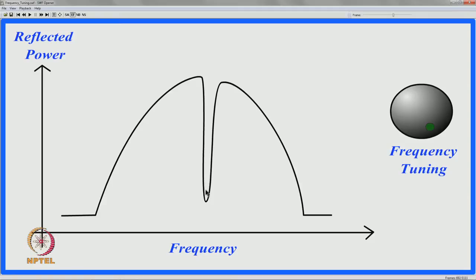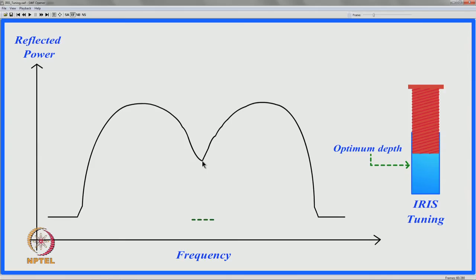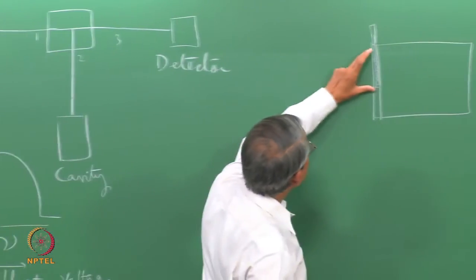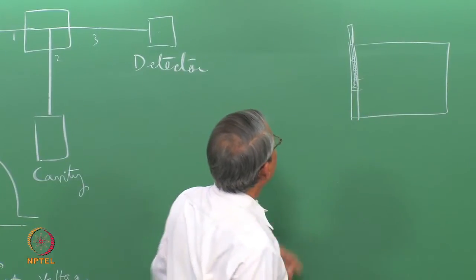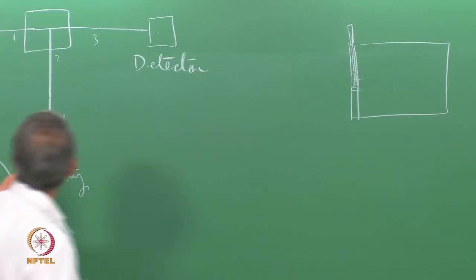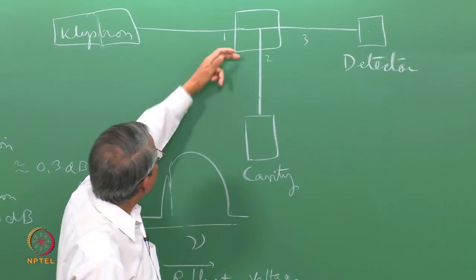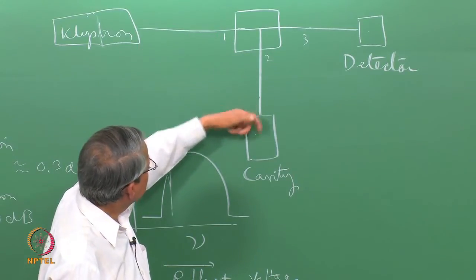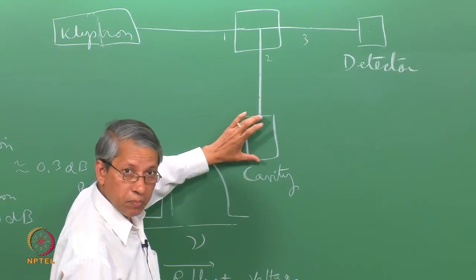Note that though much of the microwave power is absorbed by the cavity and reflection is small, it is not completely zero — the bottom of this dip is not touching zero. That means even at that frequency, some microwave power is getting reflected from the cavity. We can improve on this so that the matching is such that very little power is reflected. For that, the cavity has an iris tuner — a tuning screw in front of the iris hole. By adjusting the position of the screw, one can match the microwave entering the cavity to that which is reflected, so the reflection is minimum.